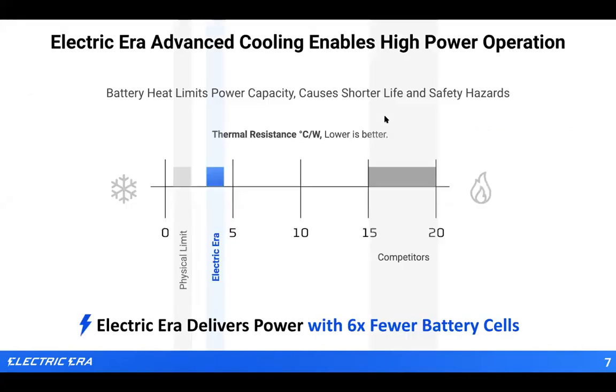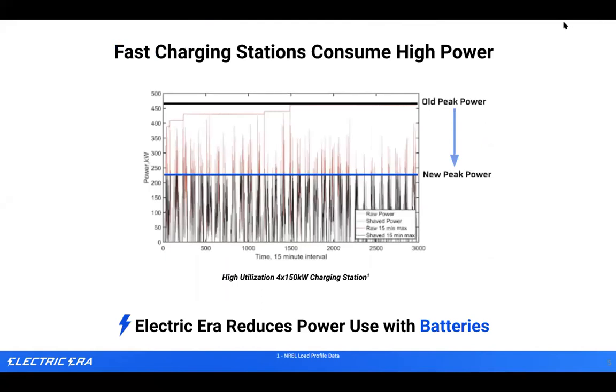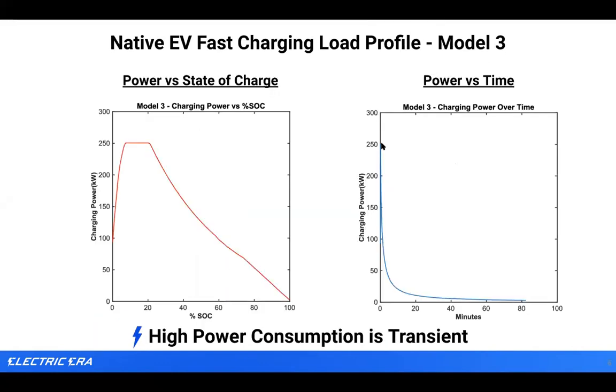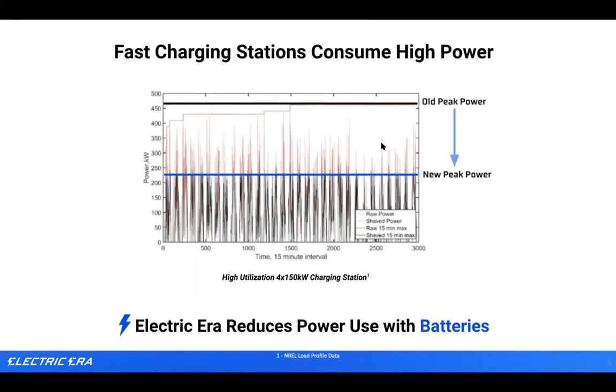That's a great question. Let me go back to that slide. What you can see here is what we call coincident loads, where multiple cars show up and happen to overlap either for the entire duration of their peak or for some partial part of it. So your worst case spikes in this graph are looking at about 450 kW. In Model 3 units, that's a little bit less than 2 Model 3s pulling peak power at once. But that's not a single car - no car can pull that much power by itself. The Porsche Taycan might pull around 270 to 320 kW. So really it's multiple cars stacking on top of each other.